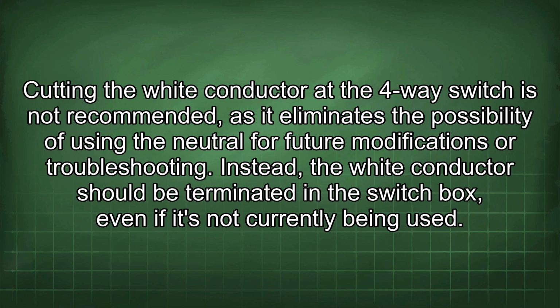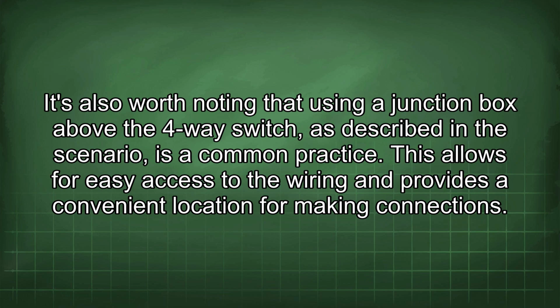Cutting the white conductor at the 4-way switch is not recommended, as it eliminates the possibility of using the neutral for future modifications or troubleshooting. Instead, the white conductor should be terminated in the switch box, even if it's not currently being used.